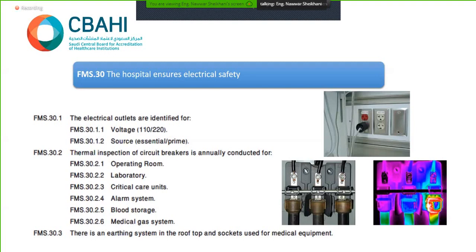In this attached photo, we labeled the essential or prime location by installing a red color, or any color, to show it's connected to the emergency power system. Thermal inspection for the circuit breaker should be done in locations like the operation theater, laboratory, critical care, alarm system, blood storage, and medical gas. This is a sample photo showing where failure might occur.